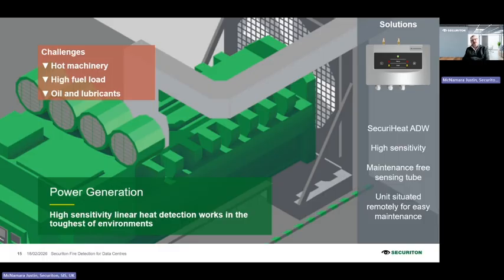We can provide a lot more information, but the ADW, which works by measuring pressure and translating that into a temperature reading, enables us to provide really good, reliable detection in these challenging areas where there might be a bit of smoke as normal as part of the operation. What we really want is to be able to define that there's been a real problem rather than some intermittent issue. Please contact us for more information on ADW - I think you'll find it's a unique solution where other forms of detection just are not appropriate and do not work.